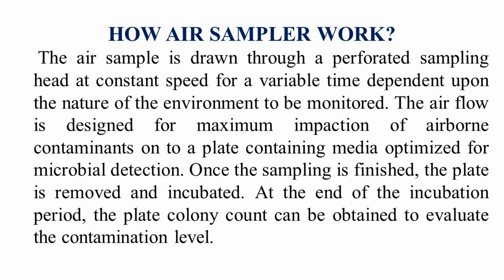Now let's understand how the air sampler works. The air sample is drawn through a perforated sampling head at constant speed for a variable time, dependent upon the nature of the environment to be monitored. The air flow is designed for maximum impaction of airborne contaminants onto a plate containing media optimized for microbial detection. Once sampling is finished, the plate is removed and incubated. At the end of the incubation period, the plate colony count can be obtained to evaluate the contamination level.